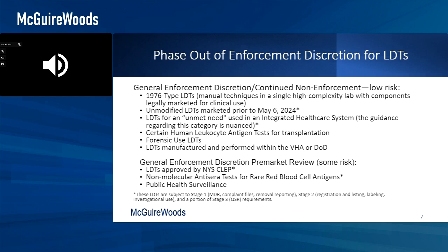There are certain categories of tests that are not subject to all of the stages of this phase-in. And the FDA effectively determined that certain types of tests, because of maybe their risk profile or how they're used, don't necessarily have to comply with all the medical device requirements. I'm going to walk through these categories, but yesterday, and Allyson was going to talk a little bit more about this later, there was a rule that came out from FDA that has a nice table in it. It's guidance for small manufacturers, for small labs, but in it, there's a nice table that goes through each of these different categories of types of tests and explains which stages of the enforcement discretion and which medical device requirements are applicable to different types of tests at which points in time.